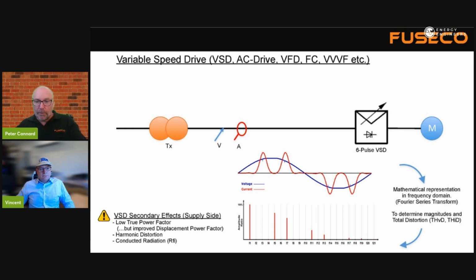So what we need to do is represent these lumps and bumps in some other way. So we use what's called a fast Fourier transform, or Fourier series transform, and we then have magnitudes we can work with. This red spike at F5 represents a frequency that is 5 times the original fundamental. So the blue one would be 50 hertz, and that first red spike, F5, could be 250 hertz. If you overlap that onto the 50 hertz fundamental, then you'll see the camel hump waveform, and so on and so on.